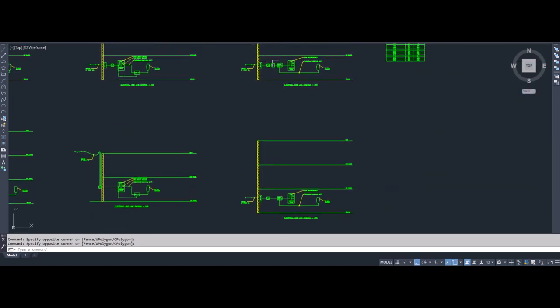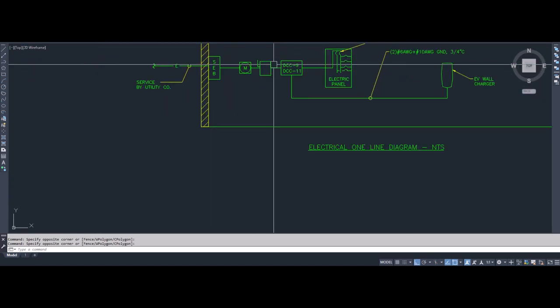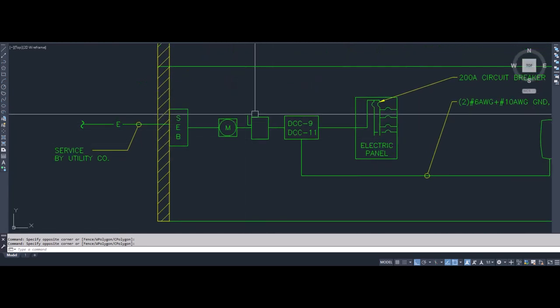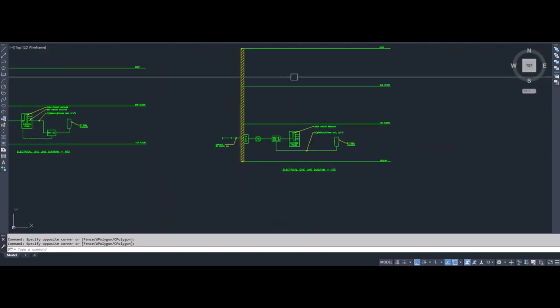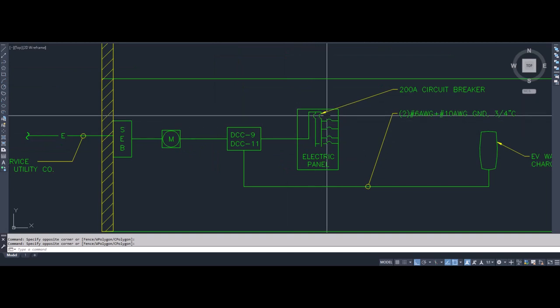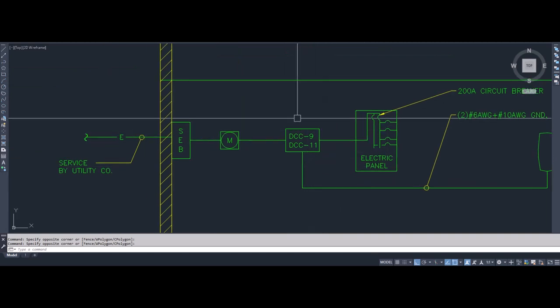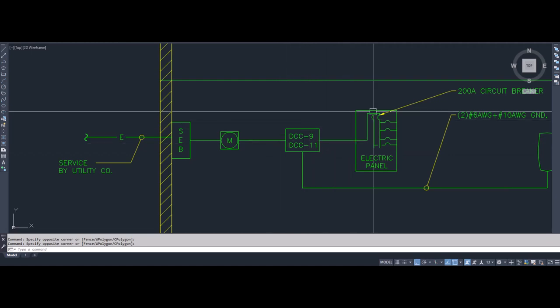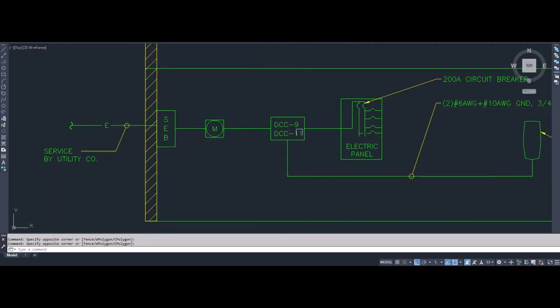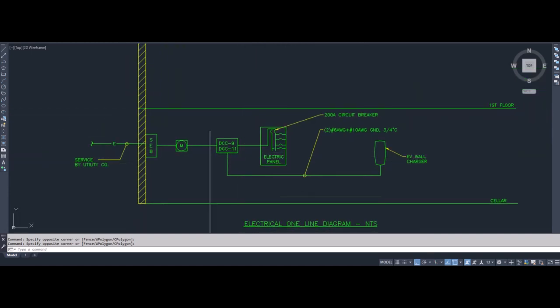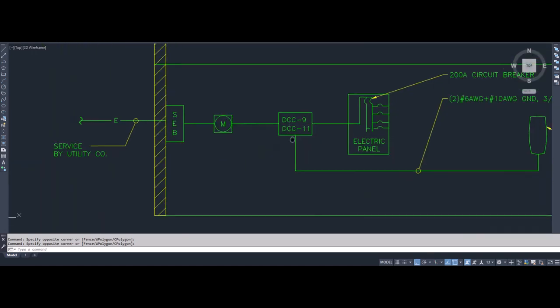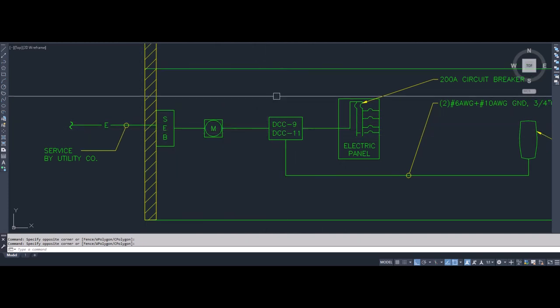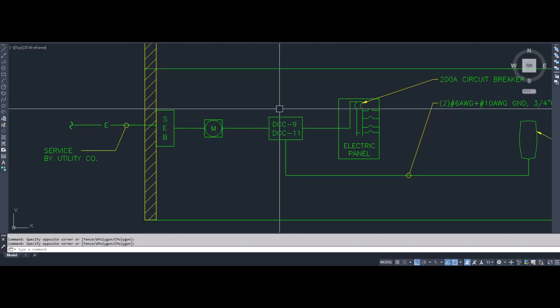Now, in a similar case where you have, rather than the main disconnect here, you only have the disconnect within the actual panel. So in this case, that's the main difference. And with the 9 and 11 installed like this, I again wouldn't prefer this situation because it's not clear if these boxes are rated for service installations. So if it's on the service, it has to be rated for service equipment, and I'm not sure if these are.